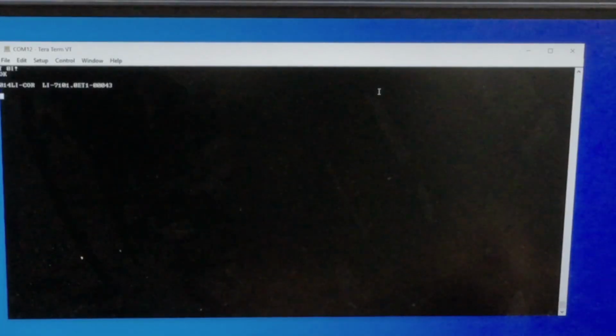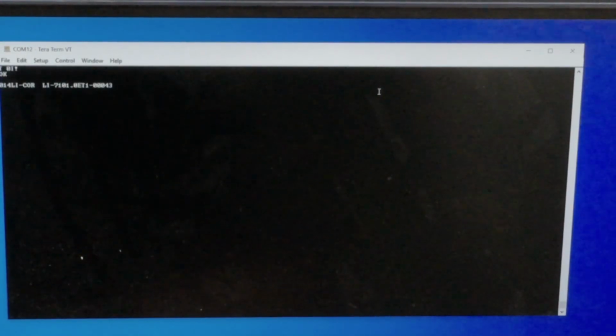By default, the 710 sensor has an SDI-12 address of 0, so when you send any command to the sensor, you need to use that address with the commands. With this SDI-12 adapter, I have to send commands in a mode called transparent mode, so every command has to start with a T. To identify the sensor, I will send the command: T, space, 0 for the address, I for identification, and then the exclamation mark which concludes the command. The sensor should respond with the manufacturer name, the model, the serial number, and what firmware it has — all that information is in the output of that I command.